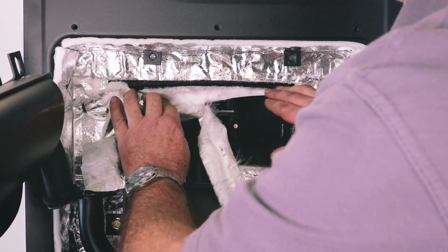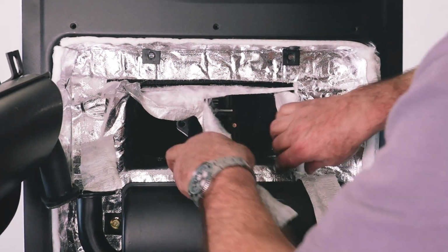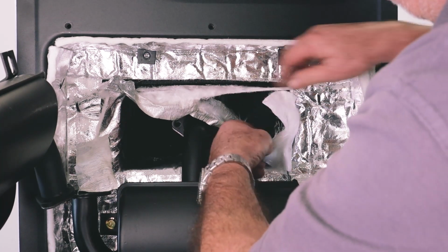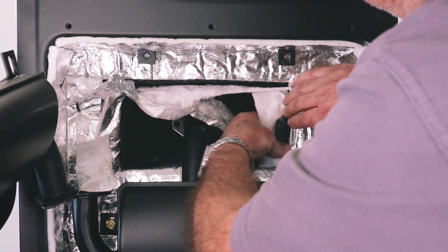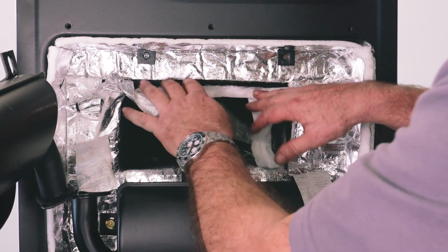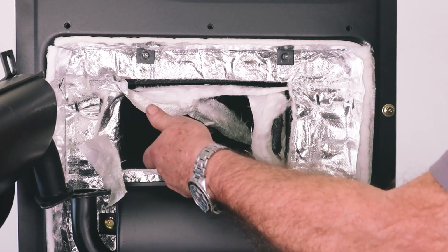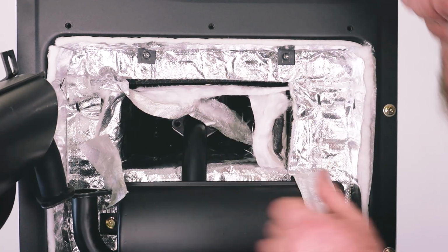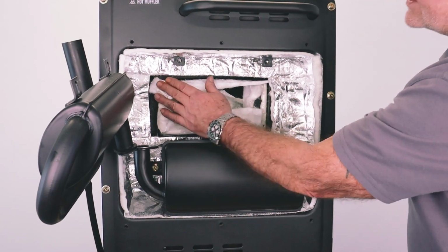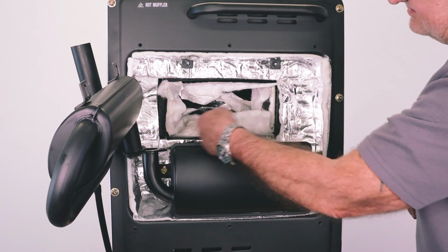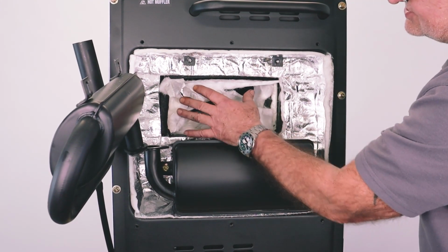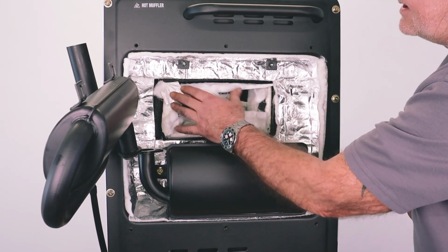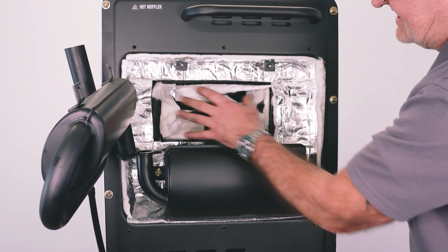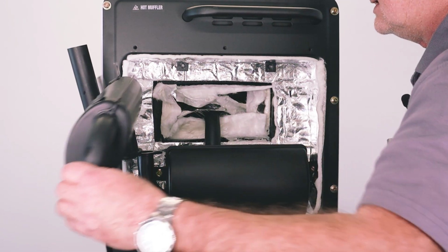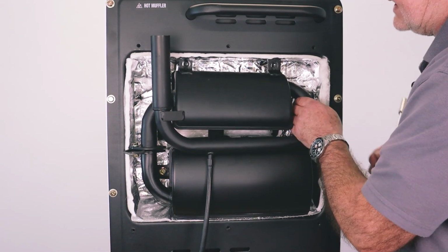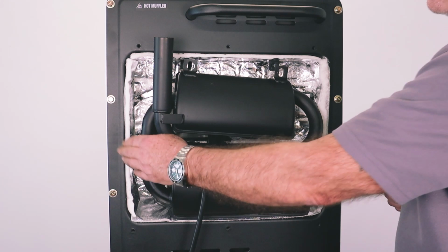I'm going to leave the tape behind inside the machine. Just peel that back a little bit, and that's going to give me the facility—I'll do the same there and the same on the bottom to be able to remove this end cover. As you can see, I've just broken the seal between this outer cover and the inner chimney, or inner air path, and folded the bits of tape and insulation back into there. So I can now hinge that back out of the way.